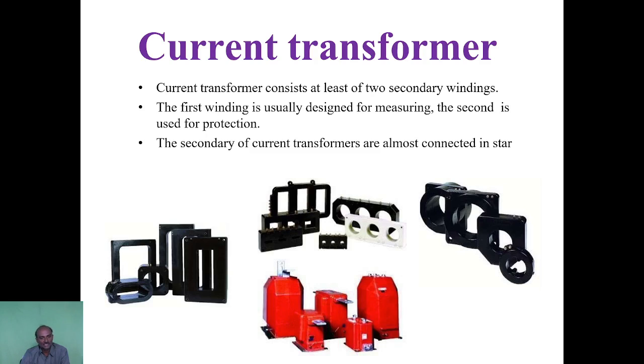Current transformers. A current transformer consists of at least 2 secondary windings, so we have two outputs to compare. The first winding is usually designed for measuring. The second is used for protection. So having 2 secondaries, we have the current transformer.